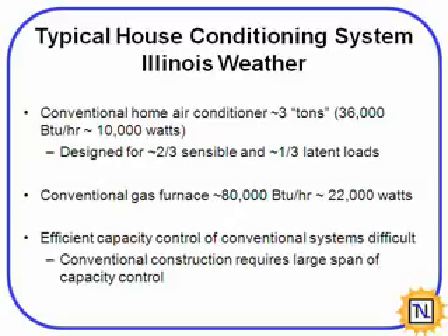Conventional gas furnace, just over 20 kilowatts for heating. And the main reason for these systems to be oversized is that they need to span these wide ranges of conditions that these houses that are not well insulated or sealed are going to be seeing. And this makes control of the capacity of these systems very difficult, and they're either on or off systems. You have programmable thermostats to help a little bit, but really there's not much capacity control within those systems.